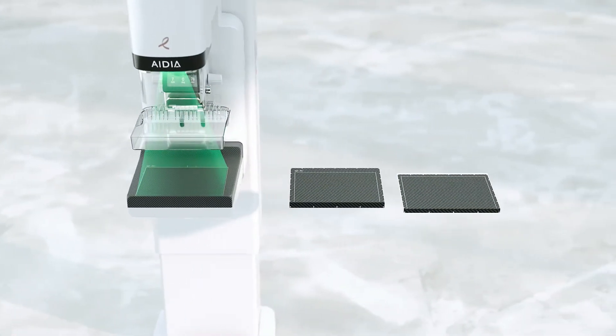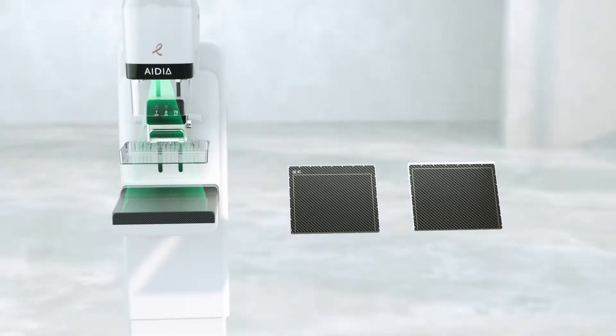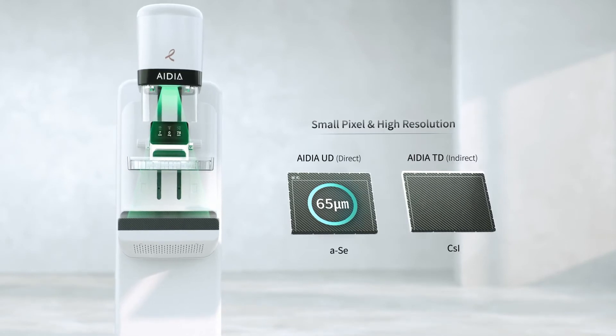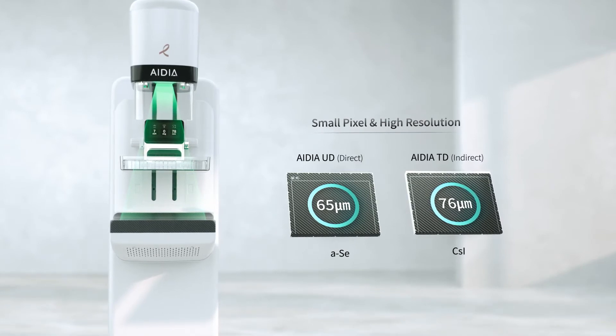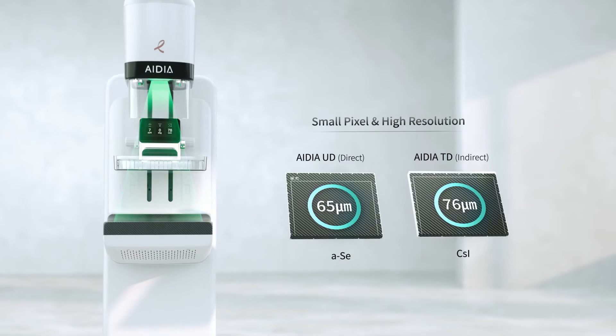With DR-TECH's state-of-the-art mammography detectors, AIDIA is available in two detector options. AIDIA's 65 micron selenium direct-type detector and 76 micron CsI indirect-type detector guarantee the highest resolution images for early detection of breast cancer.